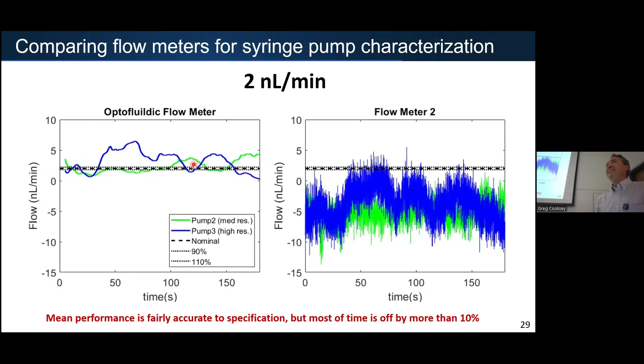I'll just show you more measurements here and move through these. What's neat about the optofluidic flow meter is, if you set a tolerance, for example 10% variation around your desired flow, you can see how much of the flow delivery you're trying to accomplish actually falls within that range. I'd propose that almost nothing you're trying to control at 2 nanoliters per minute is within any reasonable specification of that.